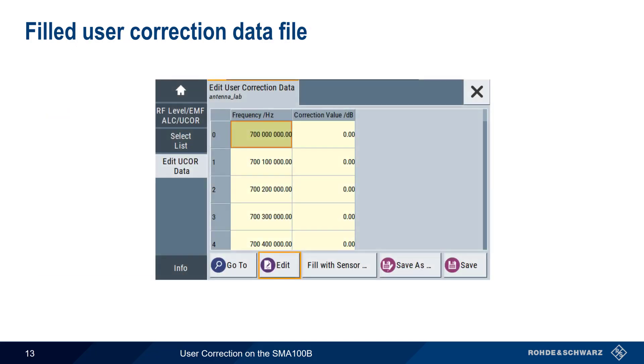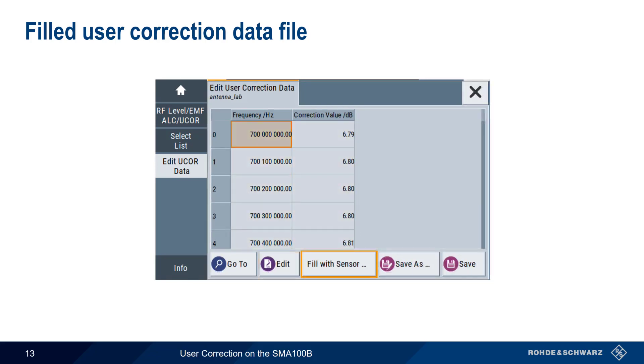Prior to filling from the sensor, we had all zeros in the Correction Value Per dB column, but after running Fill from Sensor, we see the measured values inserted into the table. If necessary, we can click on any one of these values and manually update or edit it.